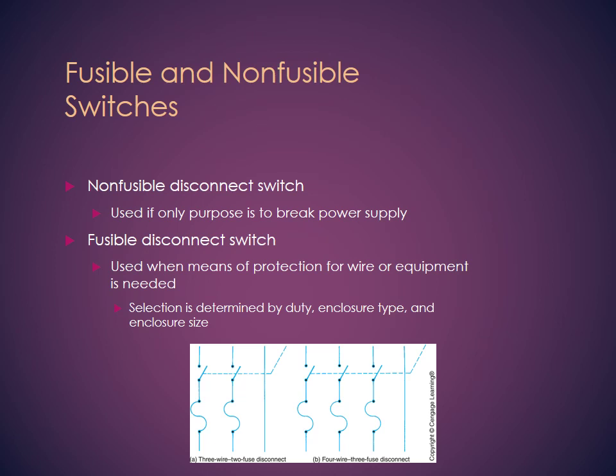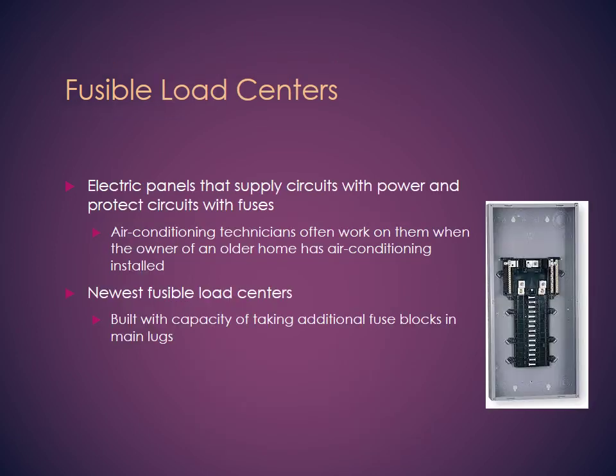Fusible or non-fusible. Again, I showed you a picture of the fusible or non-fusible. It's basically a way to increase the safety for these control panels. This is a fusible center, and again, if you see, these are fuses between all the hot lines. Again, we can use a fuse or a breaker. It's not the same. A breaker you can reset, a fuse you cannot reset. Some equipment that is inductive, meaning it has a lot of induction, like motors or magnetism involved, we might not want to use a fuse because the fuse will burn and there's a possibility of a surge with that equipment. So check with the manufacturer and the equipment requirement whether you need a fuse or a circuit breaker.